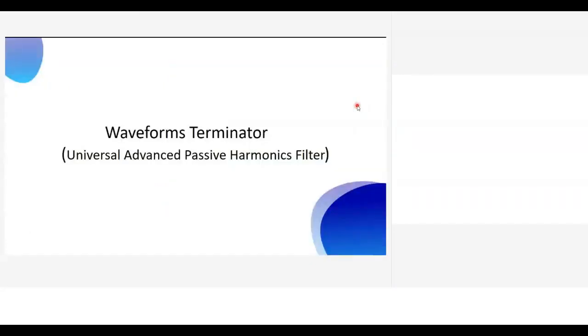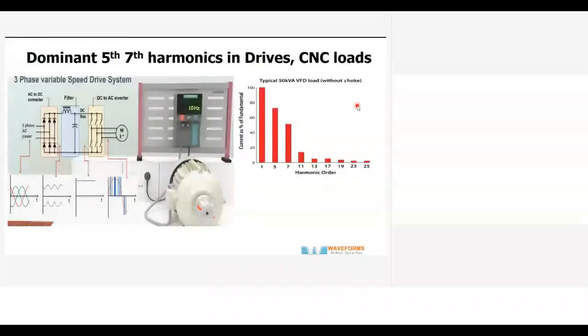I come to this thing called Terminator. We are calling it a universal advanced harmonic filter, because of these problems with the drive. You see the front end, the 6 diodes. They generate fifth and seventh harmonics and other harmonics to a limited extent.